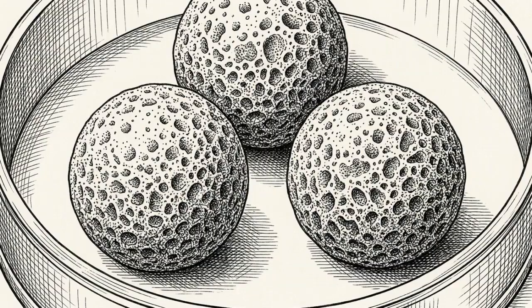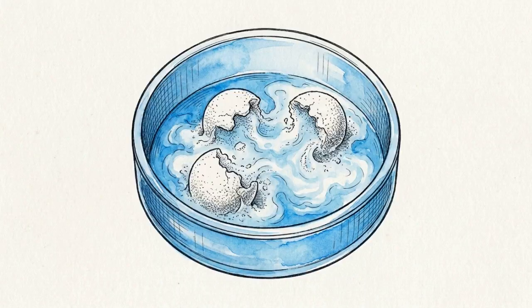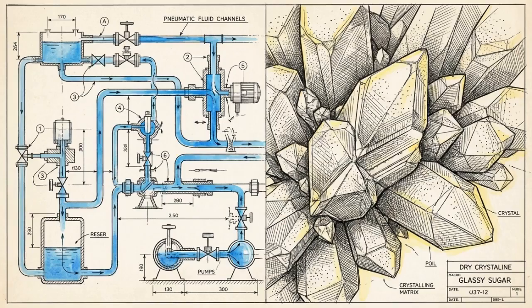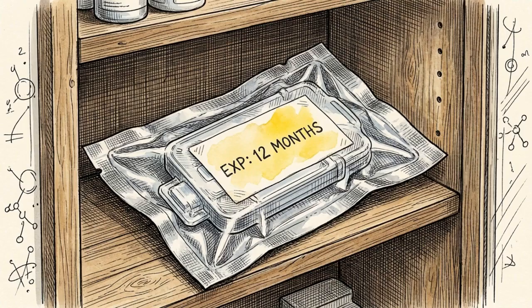The reverse transcription and hot start polymerase enzymes are preserved as lyophilized single-dose beads. They sit dormant in a reservoir, reconstituting only when the eluted sample physically washes over them. Combining advanced pressure microfluidics with glassy matrix reagent stabilization allows a highly complex molecular assay to sit shelf-stable in a clinical office for up to 12 months.